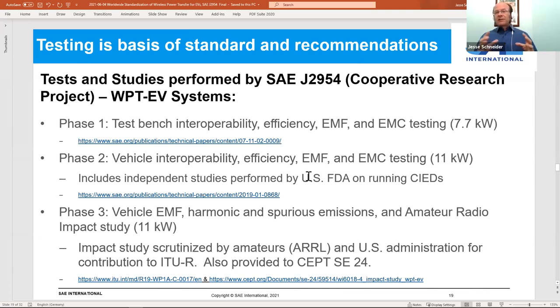We did a test with the standardized systems and SAE J2954 in conjunction with the US FDA to show there's no issue with AAMI, the Association for the Advancement of Medical Instrumentation, demonstrating the fields were low enough to be acceptable and didn't interfere with running pacemakers. All this data was published and used as validation of the final standard.